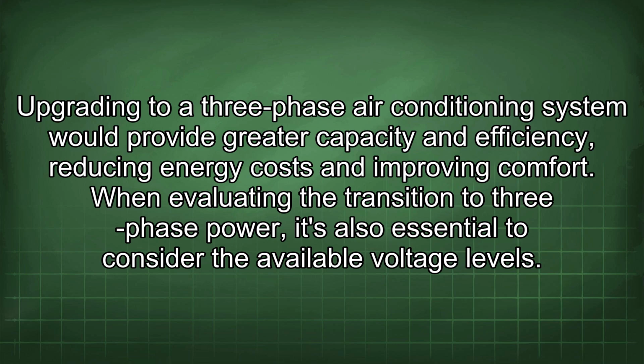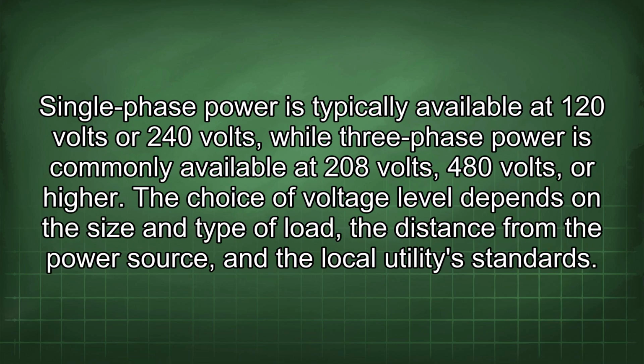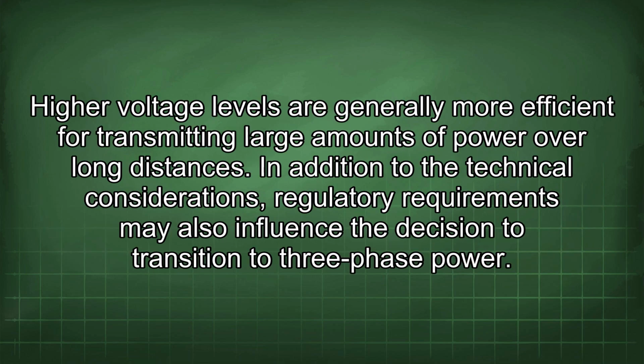When evaluating the transition to three-phase power, it's also essential to consider the available voltage levels. Single-phase power is typically available at 120 volts or 240 volts, while three-phase power is commonly available at 208 volts, 480 volts, or higher. The choice of voltage level depends on the size and type of load, the distance from the power source, and the local utility standards. Higher voltage levels are generally more efficient for transmitting large amounts of power over long distances.